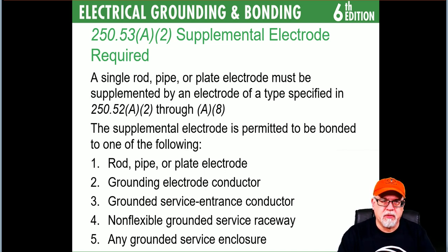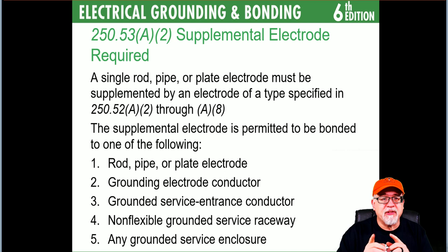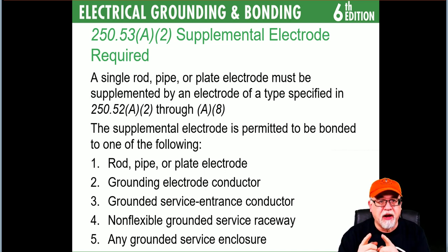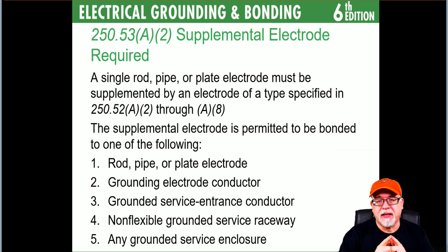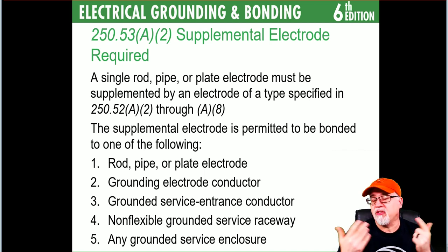A single rod, pipe, or plate electrode must be supplemented by an electrode of the type specified in 250.52(A)(2) through (A)(8) — notice it doesn't say (A)(1), the water pipe. If you can show the resistance of a single rod, pipe, or plate is 25 ohms or less, a supplemental grounding electrode is not required. In the last couple of code cycles we shifted — now you supplement always with two to start, unless you can prove it's 25 ohms or less, in which case you can go back down to one.